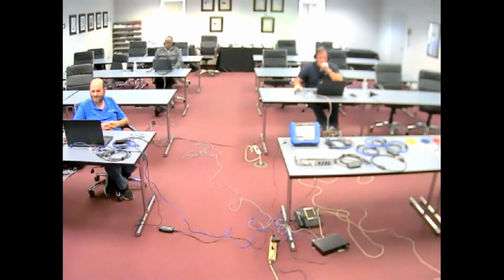Kevin asked, how is remote config done differently with Wi-Fi? If you're talking about remote config of the instrument, as Thurman demonstrated, it's exactly the same. Once you're up on a Wi-Fi network, the connection is a little different than regular Ethernet, because you have to find your hotspot or router, make that connection, and enter in any compatible security. Once you establish that connection, it's exactly the same as with an Ethernet cable. The instrument doesn't know the difference, and you don't know the difference once you're connected.